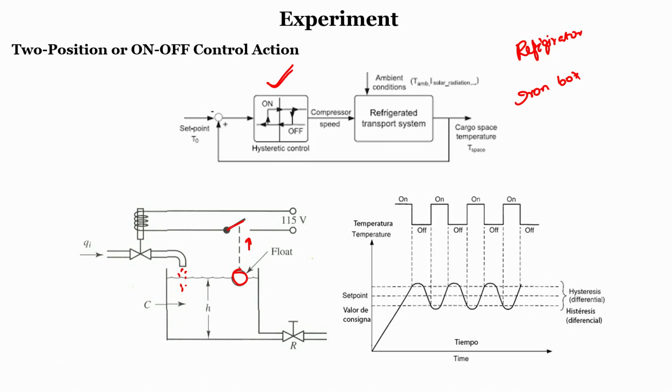So, it causes the circuit to break. As a result, since it is a solenoid switch, there is no power, so no input to the tank. Now, when the level decreases below this value, the float will come down. So, again the circuit will be on. So, it will try to maintain within this particular range.